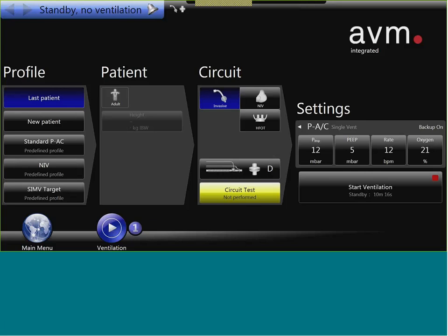We haven't tested this in the case of the coronavirus, but inside the ventilators the temperature is quite high, so we would assume that it's very hard for a virus to survive inside the ventilator. But if the customer wants to be 100% sure that no virus is coming inside the ventilator, it would also be possible to attach a HEPA filter on the air inlet as well.